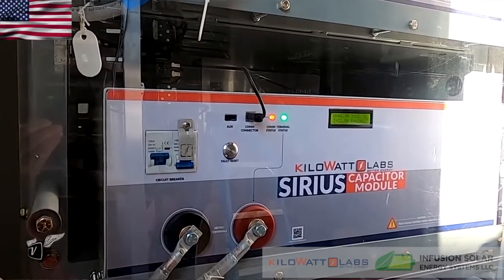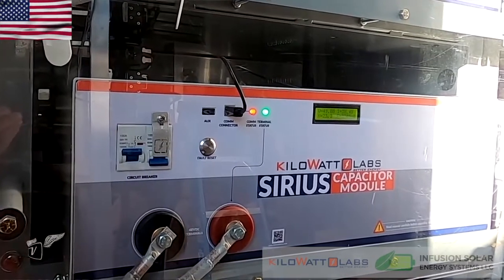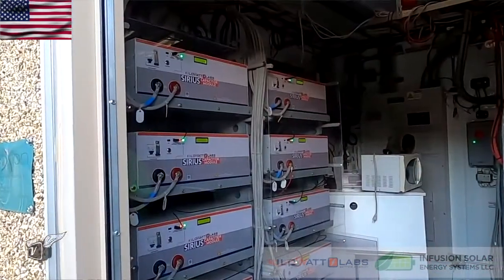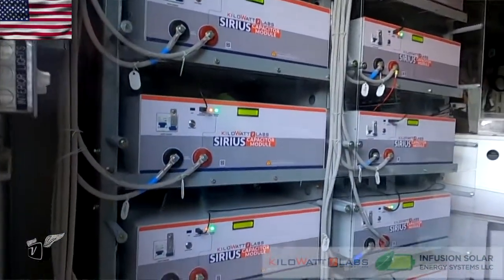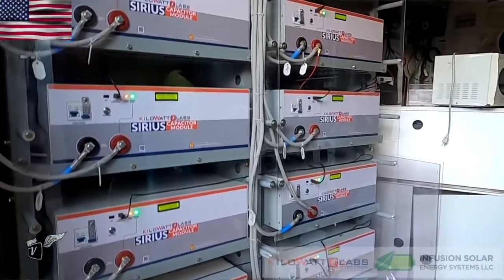From an ongoing maintenance perspective, supercapacitors have a lot more cycles than a battery. The lifetime of a capacitor is known to be over a million cycles; a regular battery you'd be lucky to get 1,500 cycles. So over its lifetime you're replacing them way less, and maintenance is zero. You can monitor them continuously — they're smart devices, we have internet connection here, we can log in and see what they're doing, and they throw alarms just like any other cell site device. And they don't outgas — with a chemical reaction you have hydrogen gas being emitted during charge and discharge cycles, but with a supercap there's no gas.